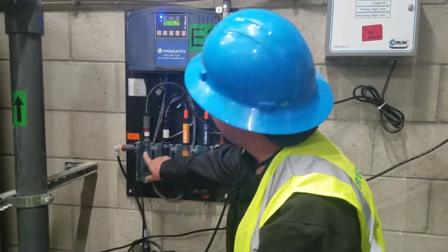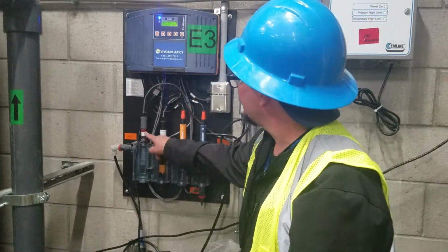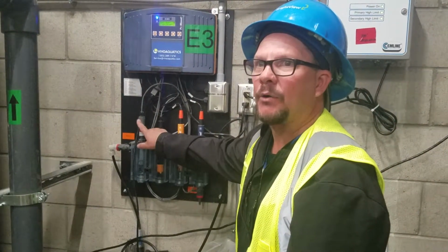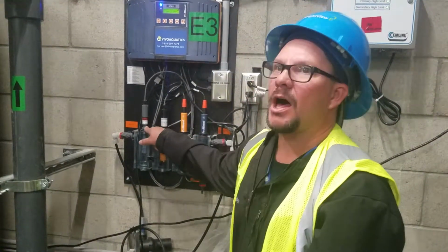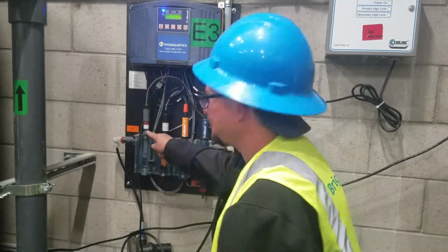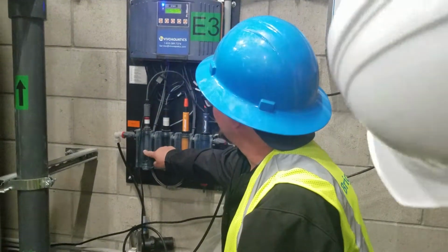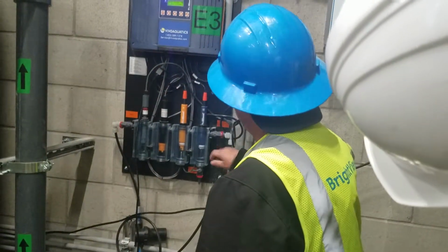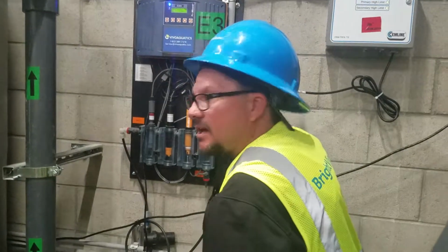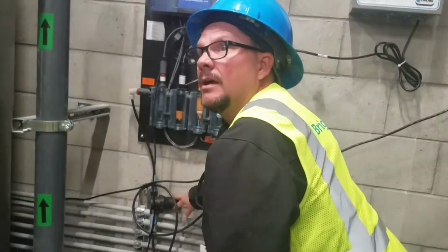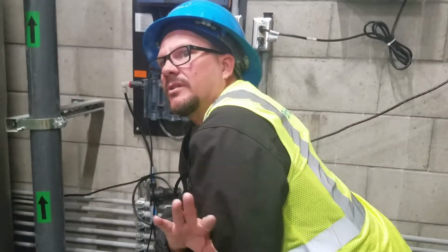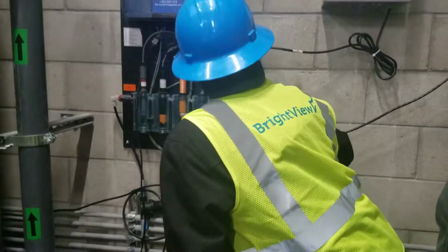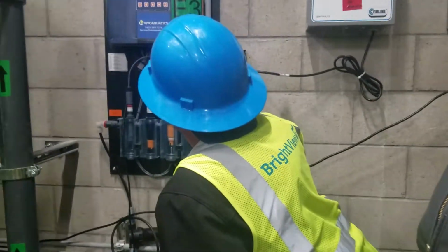And you can see there's actual levels on here where you can adjust this up and down based on what you would like to achieve for flow. Generally, I keep it all the way at the lowest setting. So we're way down here and we have this much flow to work with in there. I'm able to play with that even yet based on this being clean, based on the filters having the proper pressures, and based on the pump strainers working the way they're supposed to. Those are the factors.